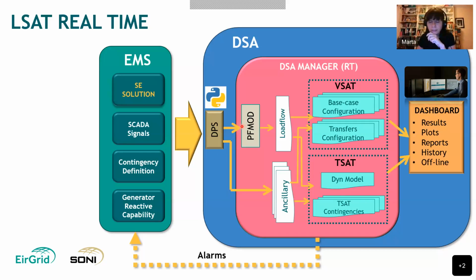So when they are transferred to that location, the first thing that happens is that we run an application called PFMod that incorporates a number of data into the load flow solution from PSSE. The PSSE file that comes from EMS doesn't have a detailed HVDC model; the HVDCs are coming as proxies with dummy loads and dummy generators. So that is replaced here by a detailed HVDC model, and a new load flow solution is reached, and the file is converted into the format that DSA tools requires in PSAT.